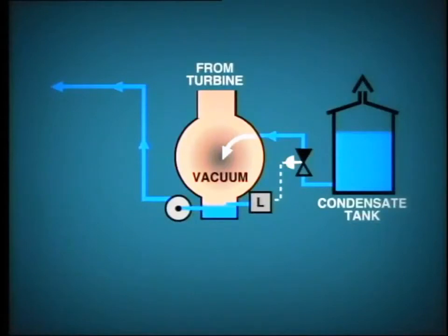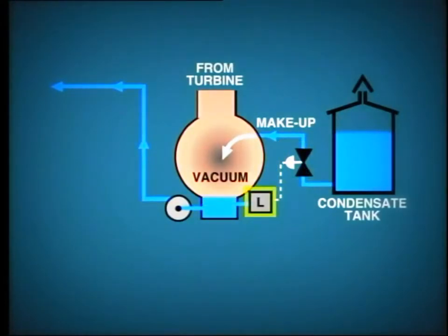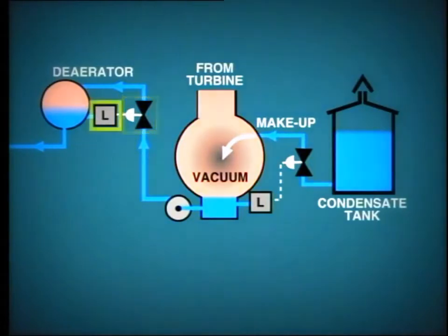Also, how is the level of condensate controlled in the deaerator? This simplified diagram shows how these objectives are achieved. Makeup water from the condensate tank is drawn directly into the condenser through this modulating control valve, which in turn is adjusted according to the level transmitter located at the hot well. Similarly, the flow of water into the deaerator is determined by this particular control valve, which is controlled by signals from the level transmitter at the deaerator.